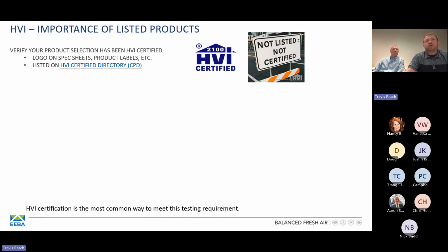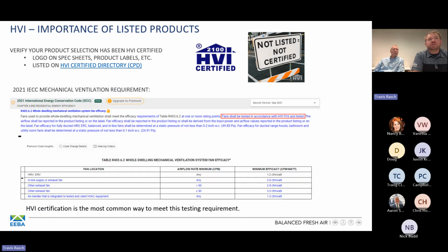Pat did hit on HVI, just again stressing the importance of HVI as it relates to if a product's not listed within the HVI directory that Pat showed earlier, doesn't mean it's certified. And so why that matters, and what you're going to see as you dive deeper into the codes, and particularly the 2021 code, is there are certain, in this case, fan efficacy requirements related to these whole dwelling mechanical ventilation systems. So you can see here the verbiage that's highlighted: fans shall be tested in accordance with HVI 916 and listed. So you're going to see here how there's a direct correlation between what HVI does and their certification process and the need for the product itself to be listed on that certified directory.